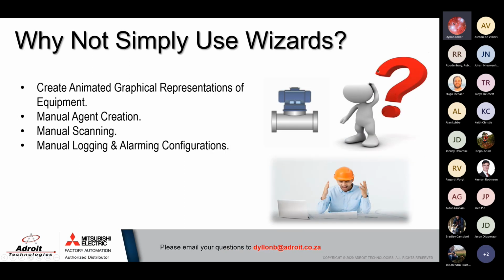So why did we bring in object model when we have wizards already as a functional way to display graphical representations of certain equipment? Well, generally, in terms of wizards, it's a very manual process in terms of setting up the graphical representation, manually creating the agents, scanning them in, and then also setting up their logging and alarming configurations. And now object model allows you to have a predefined configured instance of a wizard that can be duplicated by the click of a button.